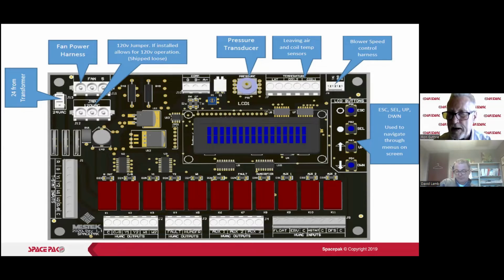All right, so when we order that hydronic coil, we need to order an additional sensor as well that we're going to use to sense the water temperature in that delay through the board here before we bring on the fan, so that we bring it on with a warm coil. It doesn't come with that coil. I've been asked, why don't they just ship it with the coil? Some coils are still shipped out for the older models as replacements or whatever. So we just have to order the extra sensor thermistor for coil 2. And I'll give you a little word about coil 2, W2, and heat pumps, and with electric heat. Okay.